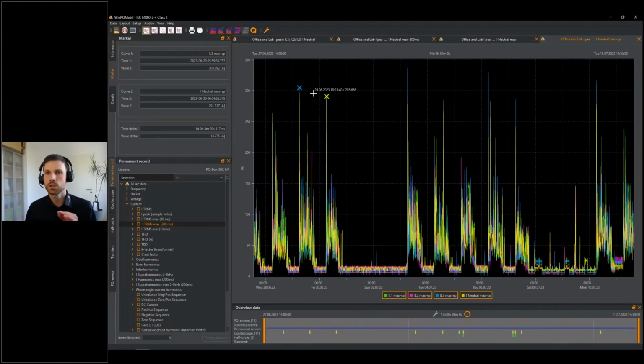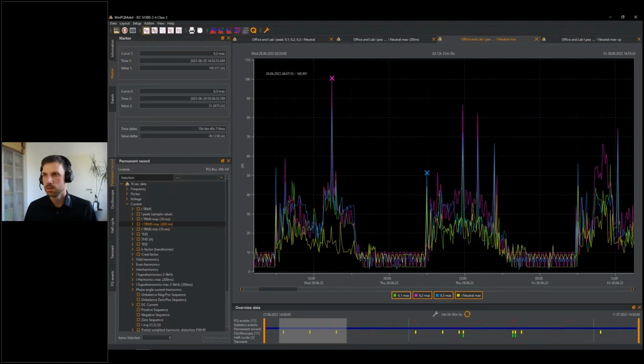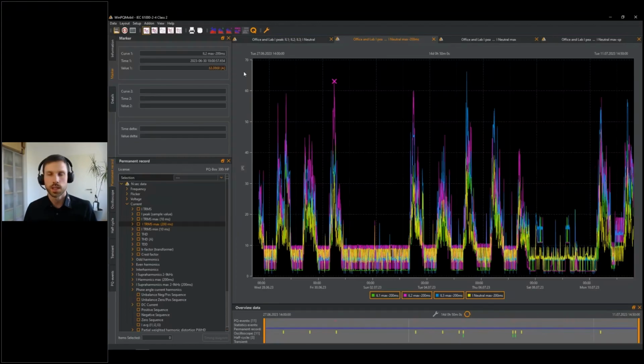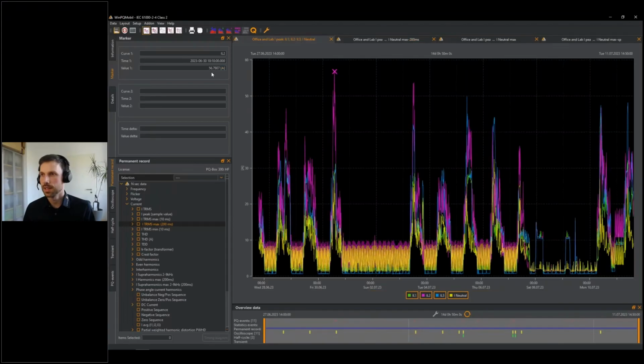So, and here we got totally different values again. So now we are in the range of 290 or 305 amps compared to the 100 amps 10 millisecond value, or 60 amps 200 millisecond value, and 56 amp 10-minute value. So different time ranges. The shorter the time range, or even going to the sampling point, the higher and more extreme the values are.